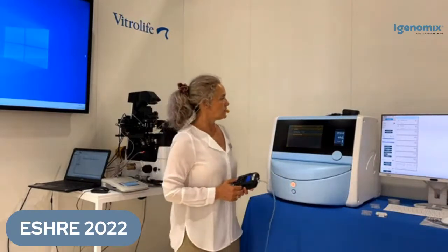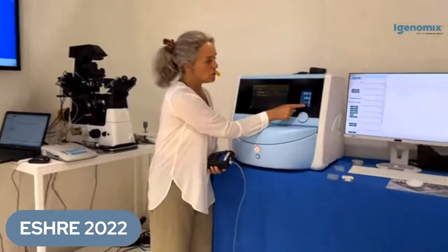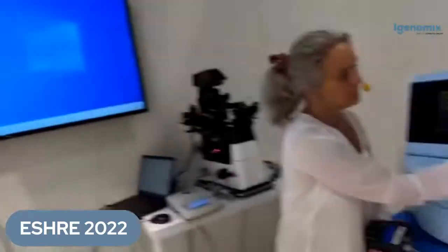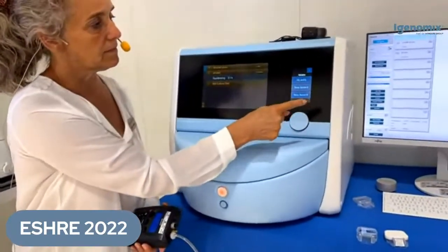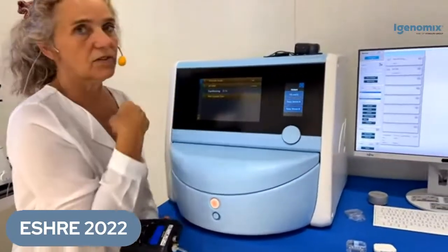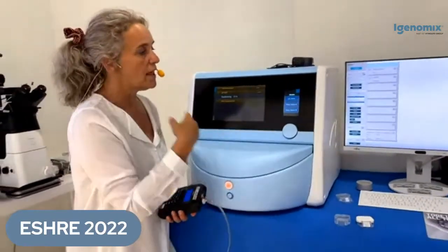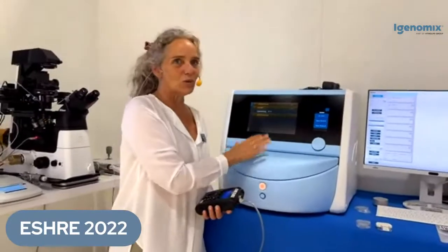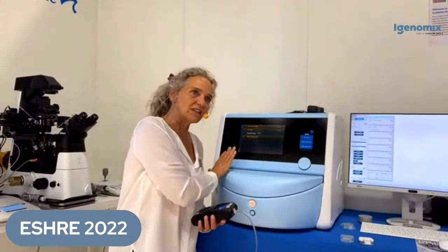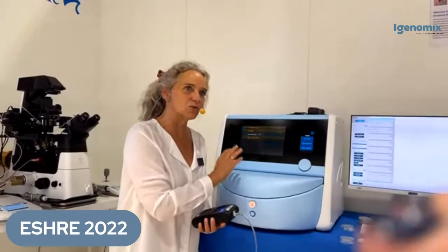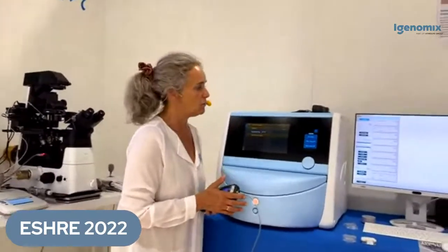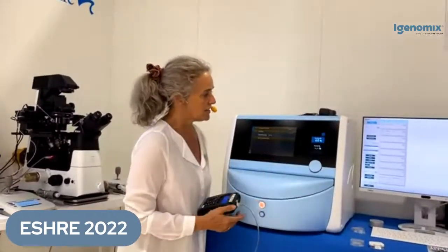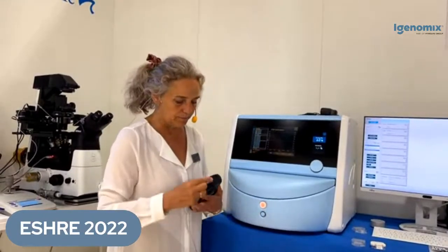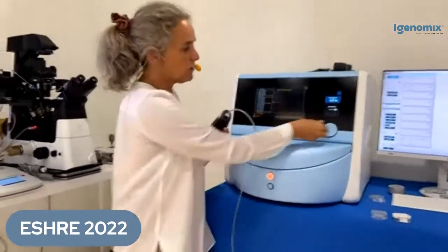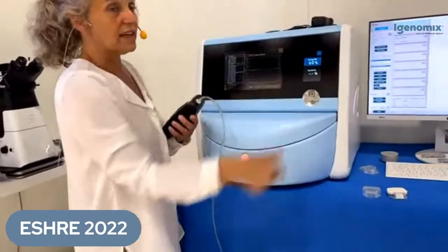What you do is start by pressing this small tool here in the corner, and we want to measure first the CO2 and O2. For this demonstration we were only able to set it up with CO2 and not nitrogen to reduce the oxygen, but the principle is exactly the same. So for this demonstration I'll only do it with CO2. So I press here and you can see the CO2. Then I open up here where you get access to the input chamber.